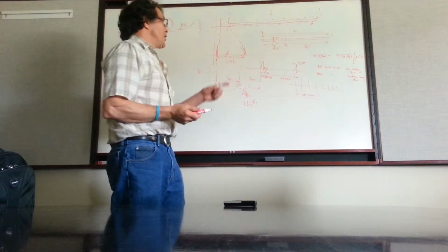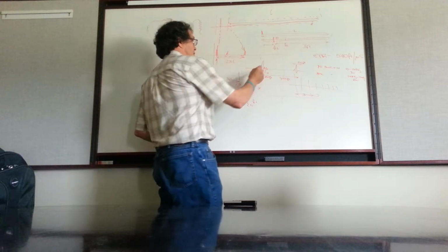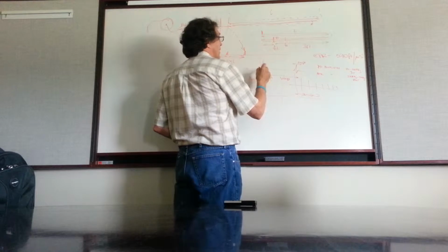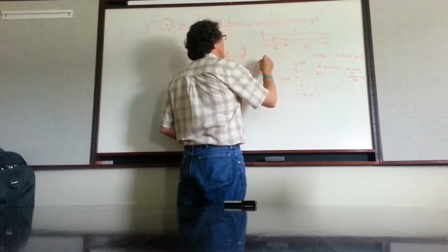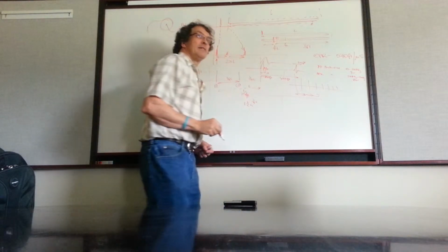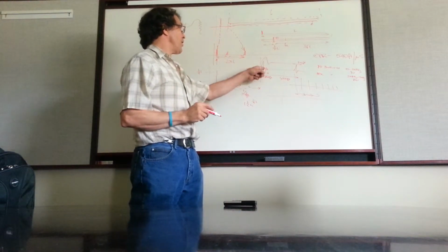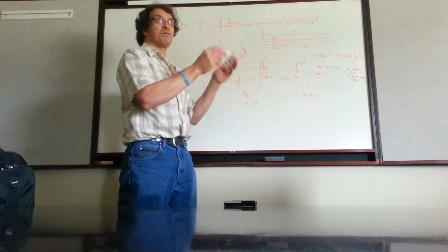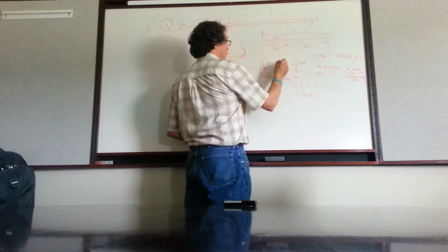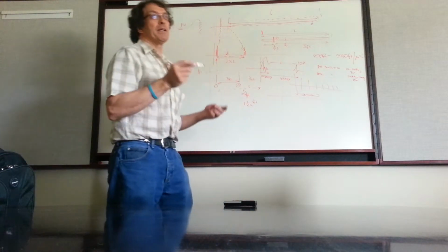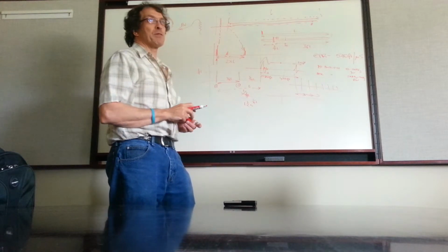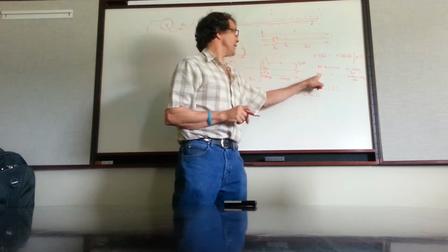The only difference to you is that it changes the shape of the pulse. Where the PDSL might look like this, the PD one might look like that, because it can't actually resolve the high frequency stuff, so it blobs it over. I got you. Now if your fault is here somewhere, then the PDSL amp is fine. It's only when the cables get real short that you need this guy.